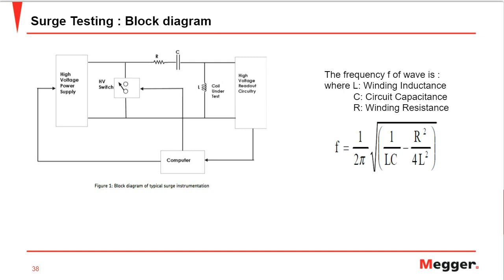So just to reiterate, if it is a sudden increase in frequency, that is an indication of arcing or turn-to-turn fault. And it also depends on the coil and the location of the arcing short. So the magnitude of the surge waveform may also slightly decrease, as we have seen previously, that most of the turn-to-turn faults occur at the early turns.